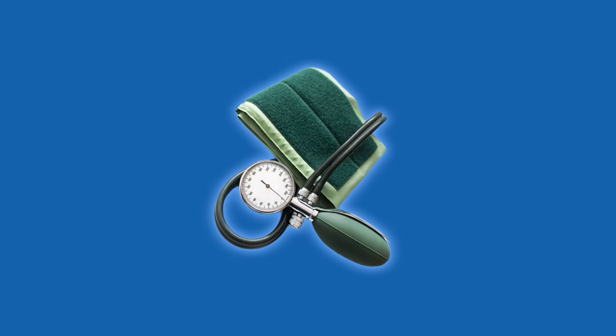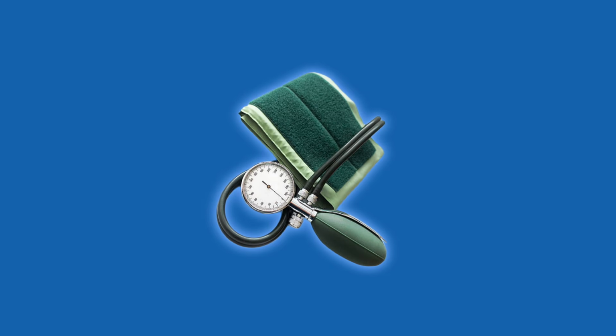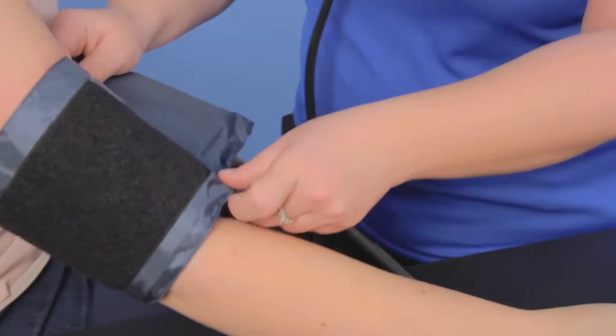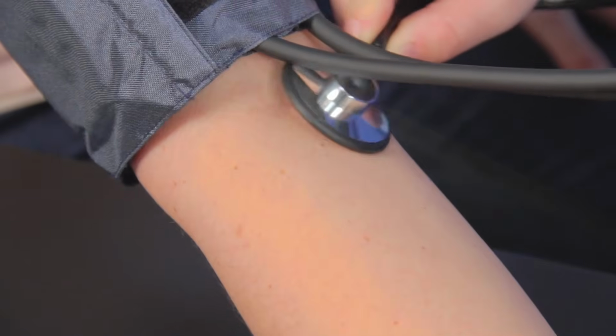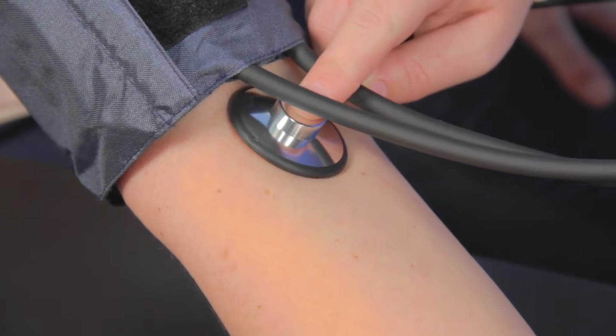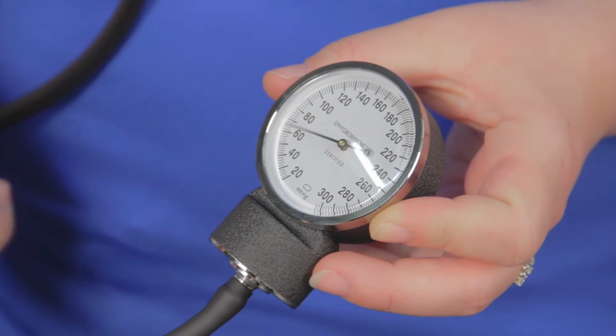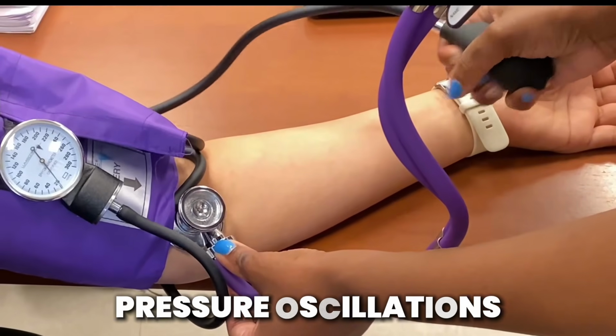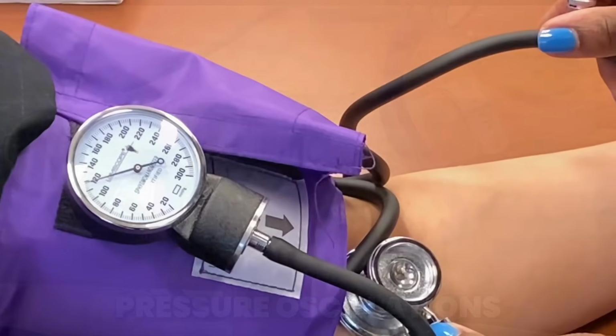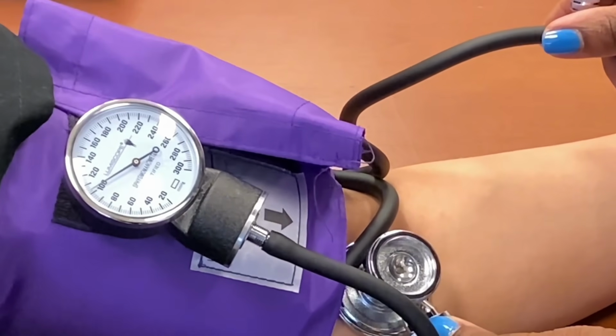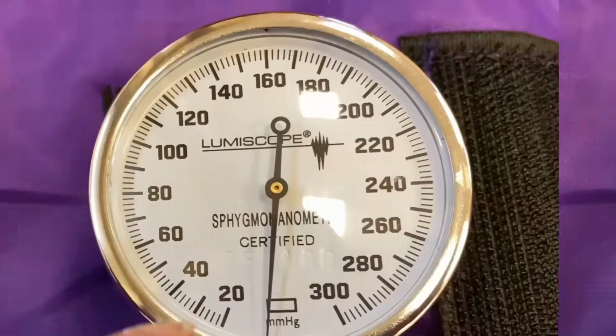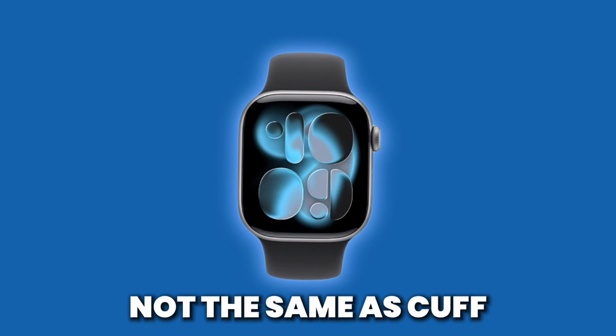Now let's talk about what it does not do, because this is where expectations tend to drift. It does not replace a traditional cuff. Upper arm cuffs use what is called the oscillometric method. They inflate around the arm. They temporarily restrict blood flow in the brachial artery. They measure pressure oscillations as the cuff deflates. From those oscillations, they calculate systolic and diastolic pressure directly. That is measurement. The Apple Watch does not do that.